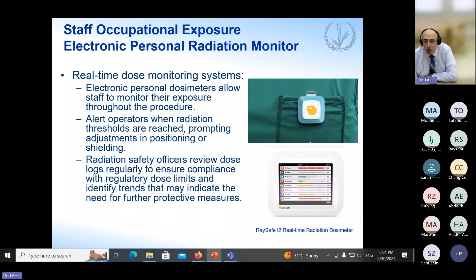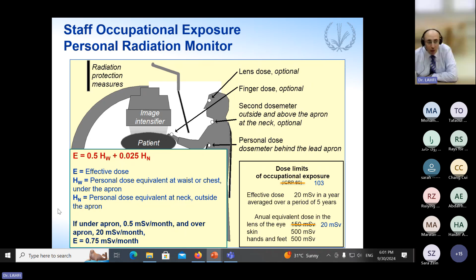This is a RaySafe i2 real-time radiation dosimeter. We can see the doses in real time for all the staff inside the interventional rooms. This is very interesting. As you know, in IR we use not one film badge, but two personal dosimeters, or perhaps 3 or 4, but 2 at least. The first one is behind the lead apron, the second one is outside and above the apron at the neck level. Also, we can have eye dose and finger dose dosimeters, and we can calculate the effective dose from this equation for the radiation protection measure.